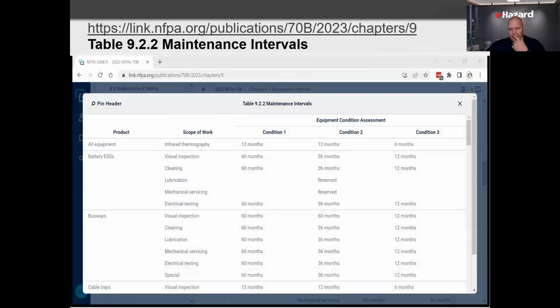Here's the table, table 9.2.2 in chapter 9, which sets out our maintenance intervals. Notice it doesn't give a specific type of activity that we're going to get into. For things like busways, we do a visual inspection—if it's in condition 1, we do a visual inspection every 5 years; if it's in condition 3, we do it every year. But it doesn't tell us what that visual inspection is looking for.